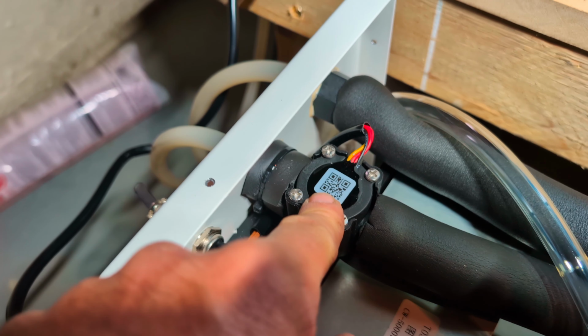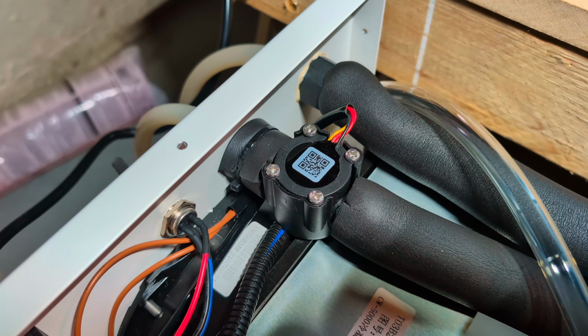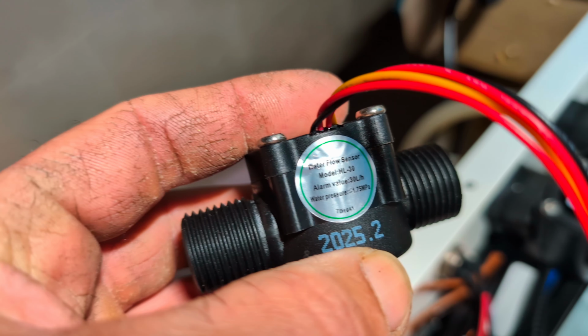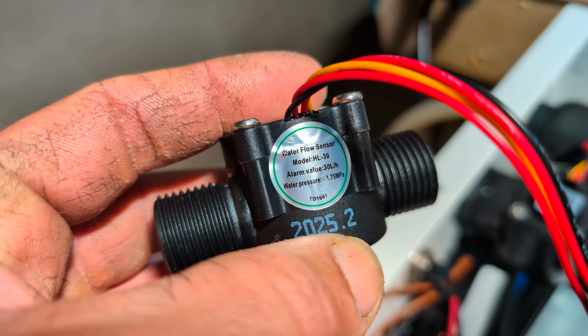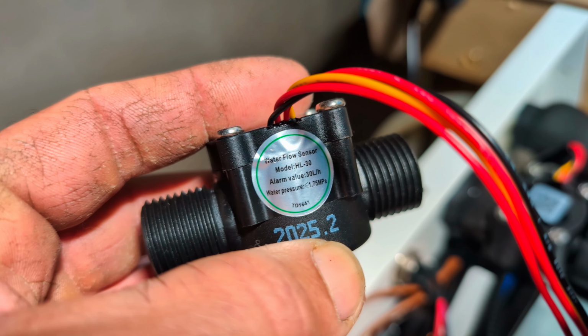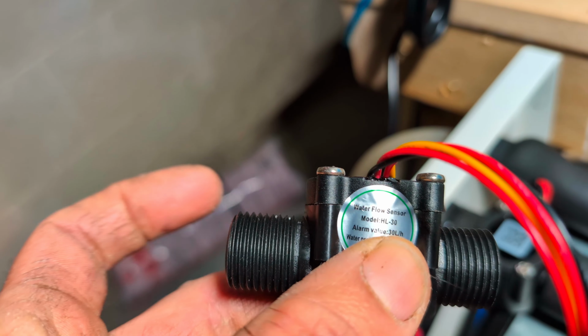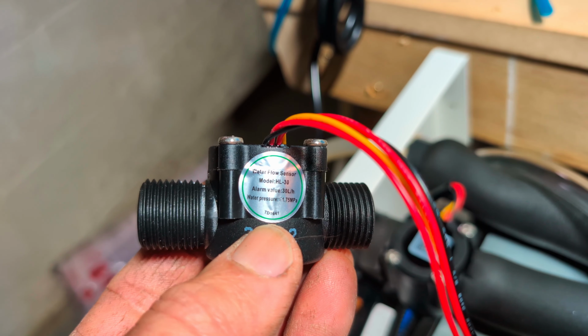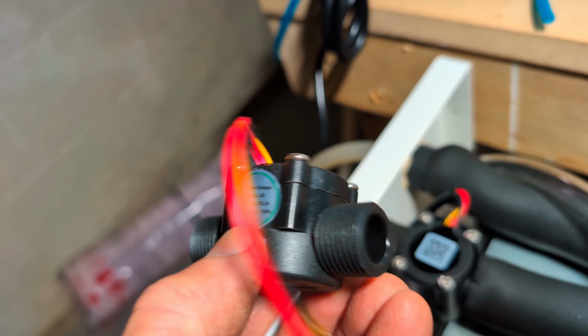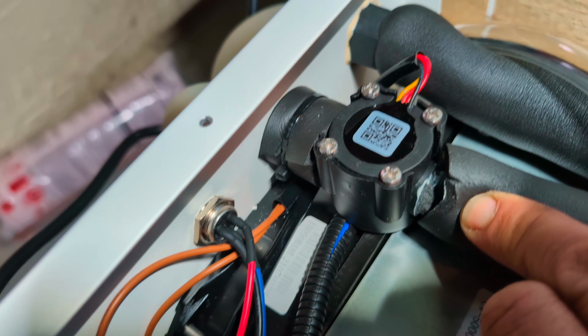So I went online. You can find the correct flow switch online pretty easily. Here's the old one. There's the, if you can see, you find any switch that has those specifications. Now, what this is actually, the top is the old, the bottom is the new component, and you can see it's got this threaded ends on it. What you'll find when you peel the foam back here is that there's no threads, and it's a much thinner tube that connects. But all you have to do is replace the top.